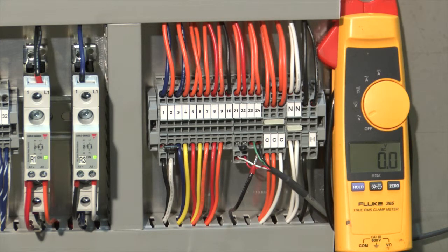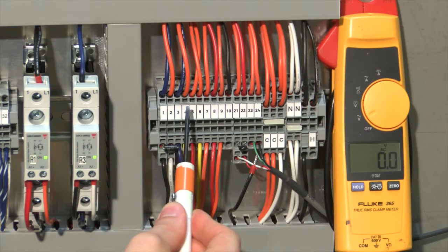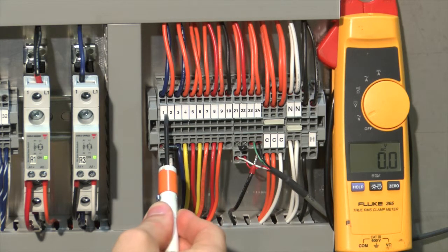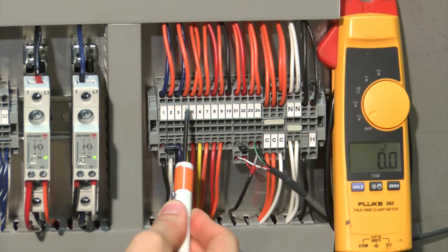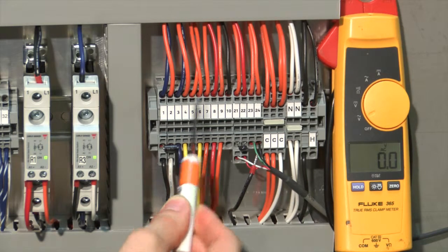The final test for transducers not operating is to verify the transducers themselves are receiving 48 volts AC. If your humidistat is calling for humidity, you verified your transformer power is good, your fuses are good, and the solid-state relays are both lit, your transducers should be receiving 48 volts AC. You can verify this on terminals 1 and 2 and 3 and 4. Terminals 1 and 2 power row A, terminals 3 and 4 power row B.